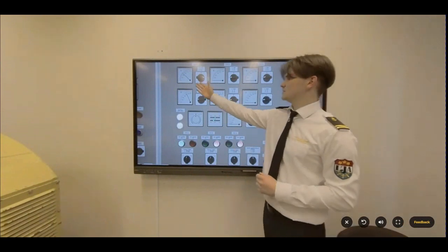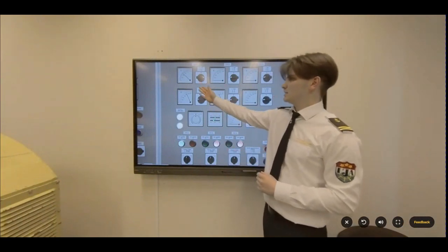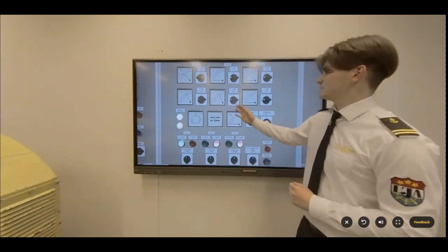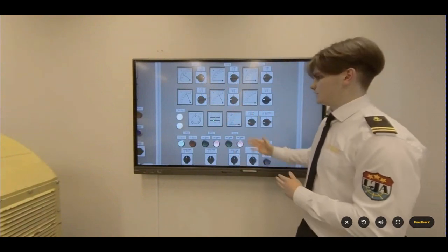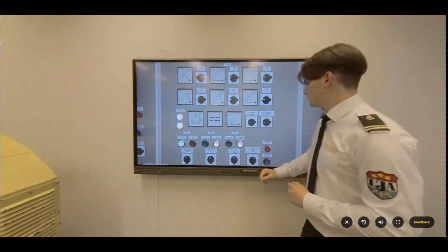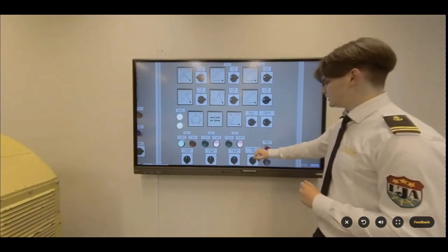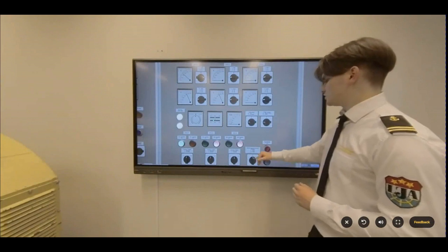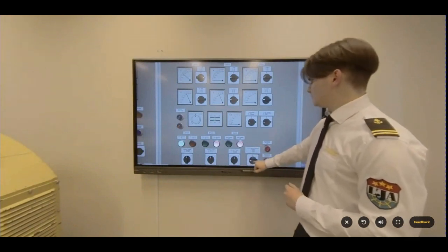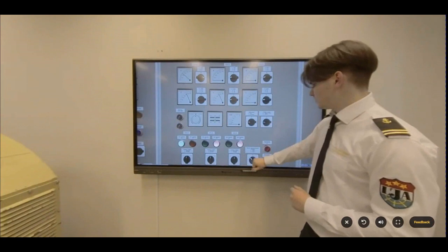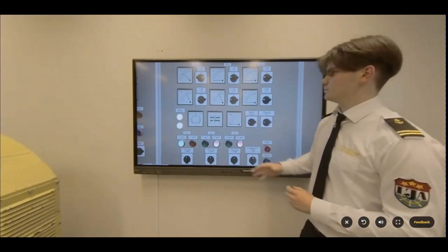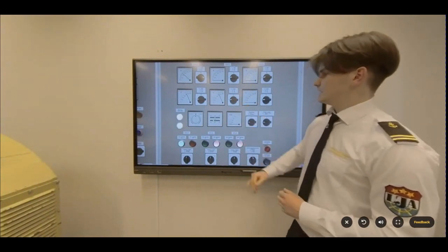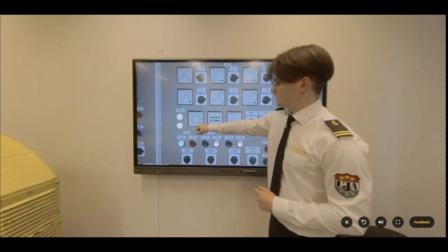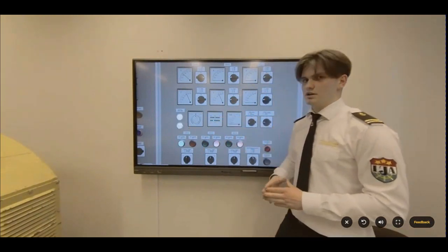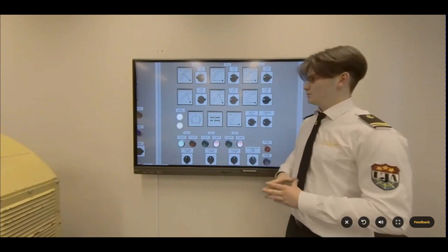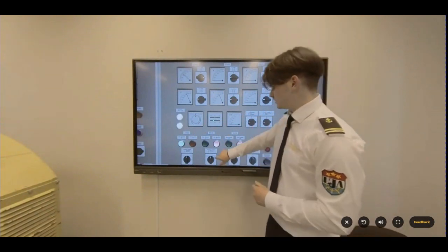Generator number 1 is now running, producing electrical power. Generator number 2 is not connected yet, and we have to synchronize it with number 1. Here we can see the switch for the synchronization selector. We can choose any generators to synchronize, and since we want to synchronize number 2 with number 1, we choose the second one. On the indication, the lamp is rotating in the anti-clockwise direction, so we should make it rotate in the other direction.